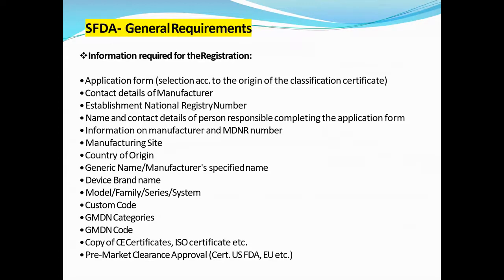So this is the general information required for the registration of a medical device with the SFDA. First is the application form, which is common. It is a selection according to the origin of the classification certificate. Then the contact details of the manufacturer, establishment national registry number, name and contact details of the person, information on the manufacturer and MDNR number, manufacturing site, country of origin, generic name, device brand name, model, customs code, GMDN number, GMDN code, copy of the CE certificate, ISO certificate, then pre-market.